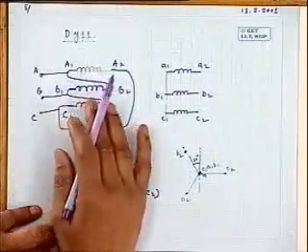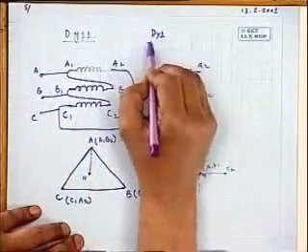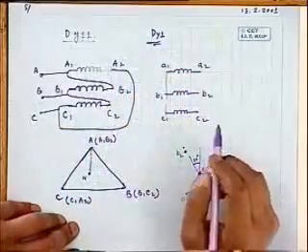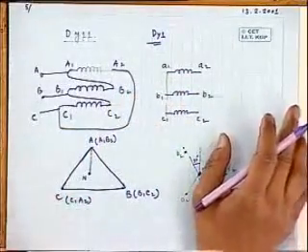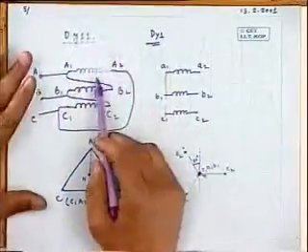This connection diagram, say Dy11: with this primary connection in this fashion, if you had tried this connection for realizing Dy1, then it would have been nice. Are you getting what I am trying to tell? Suppose I wanted to realize first what I have showed, Dy11. Now primary is this three winding, secondary. Now I connect delta arbitrarily, but correctly. Only two ways you can connect deltas correctly, this way or that way. Otherwise that voltage will not be 0 when you close it.